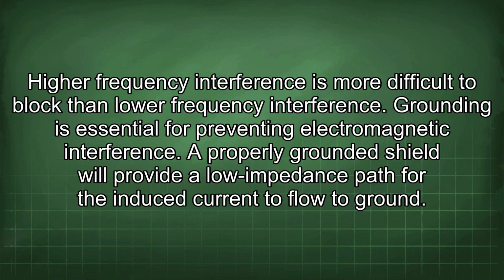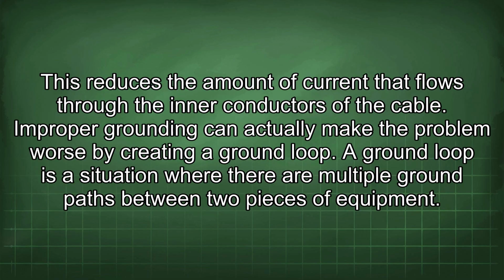Grounding is essential for preventing electromagnetic interference. A properly grounded shield will provide a low impedance path for the induced current to flow to ground. This reduces the amount of current that flows through the inner conductors of the cable. An improper grounding can actually make the problem worse by creating a ground loop.